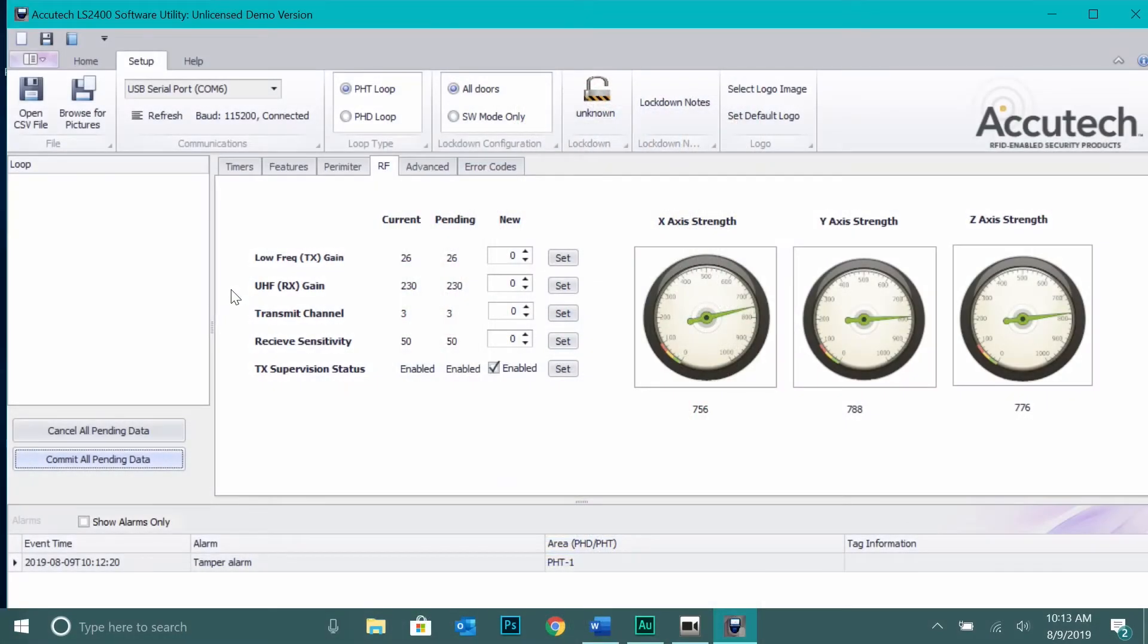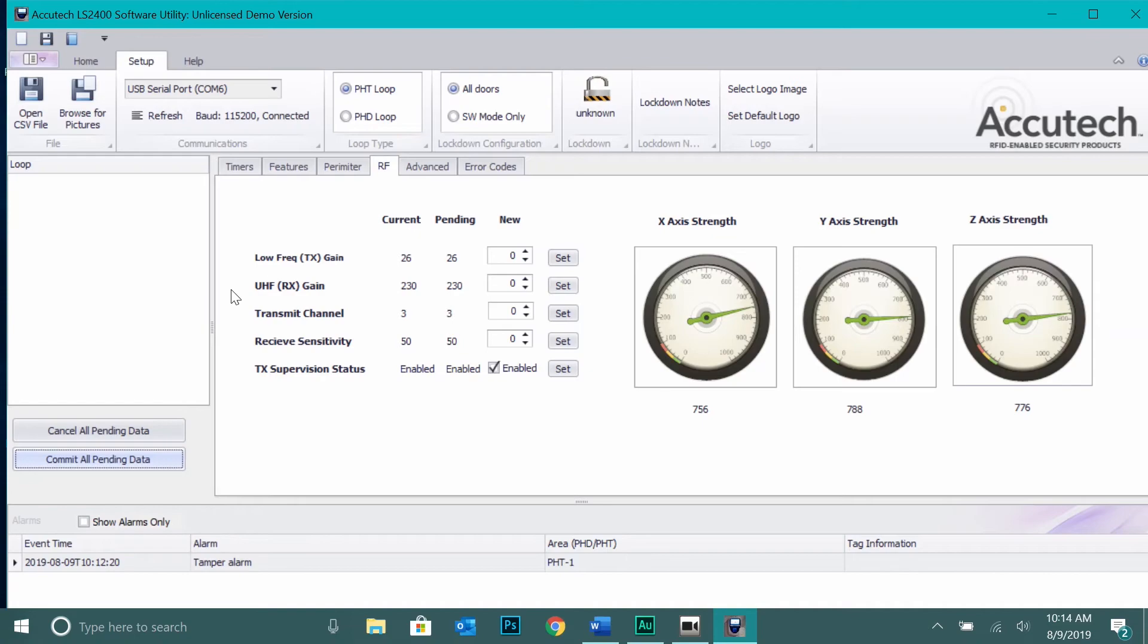After the door controller is in phase lock, return to the RF tab of the utility. Below you will see values of the antennas. Ensure that these values are 750 or higher. If not, continue adjusting the tuning capacitors until this is achieved.